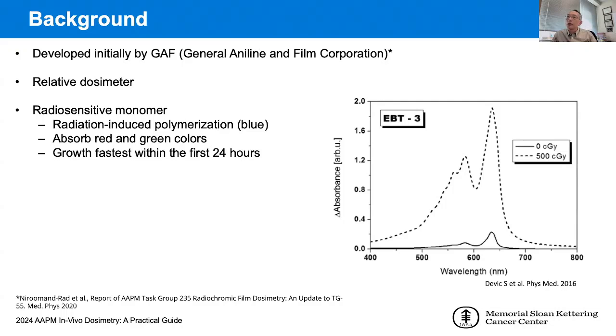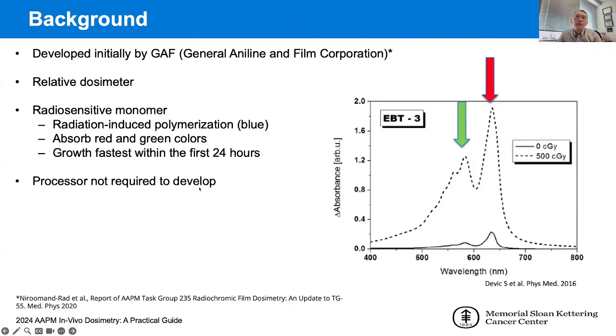As you can see on this plot, the solid line here is the unexposed absorbance of the film when it gets scanned in a scanner. If we expose it to, say, 500 centigray of radiation, the shape of the curve would change, and it turns blue, meaning that it will absorb red and green colors, as shown here. So these two peaks represent the high absorbance of the film and the reason for it turning blue. And this polymerization process is the fastest within the first 24 hours. Unlike radiographic films, developing is not required for radiochromic film.